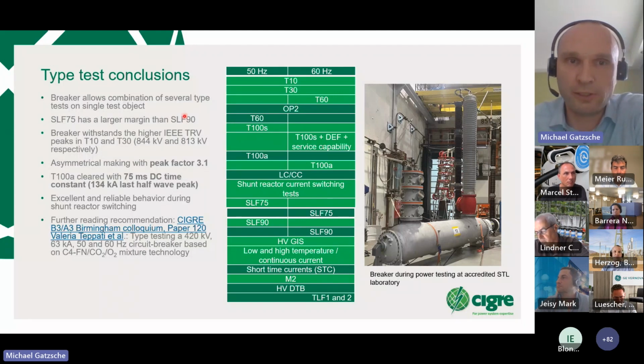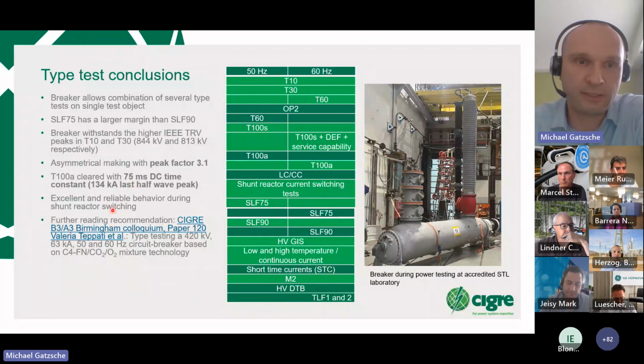For example, T10, T30, T60 were done on the same test object. We have some general learnings from this test: short line fault 75 has a larger margin than SLF90, and the breaker also withstands the higher IEEE ratings or TRVs for T10, T30. We have 75 milliseconds DC time constant for the T100A, and as we've seen in the previous slide, it has really excellent and reliable behavior during shunt reactor switching.